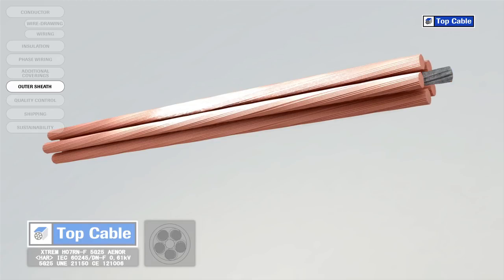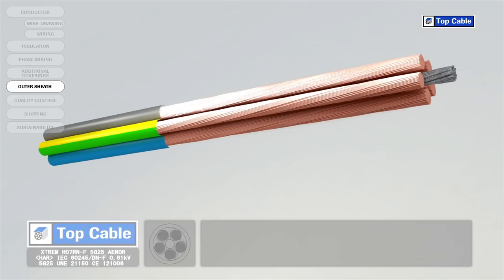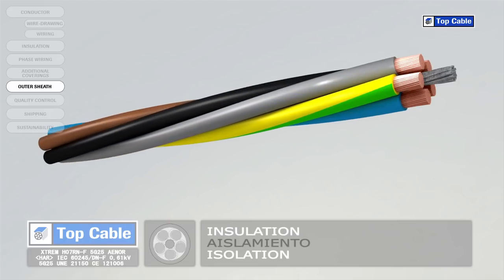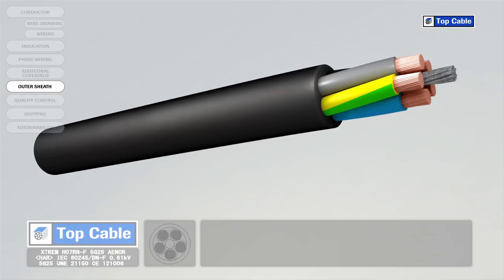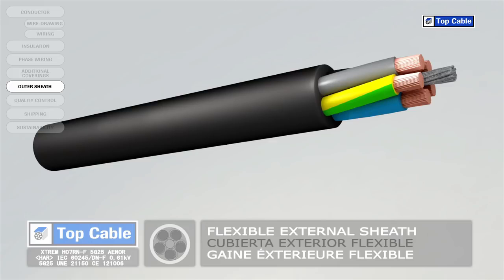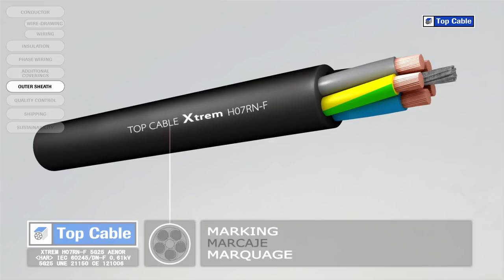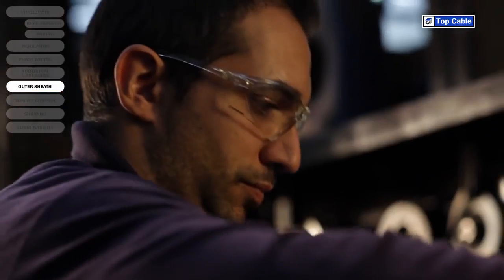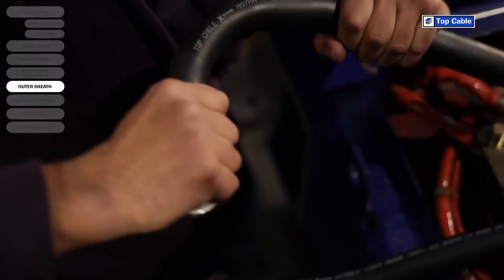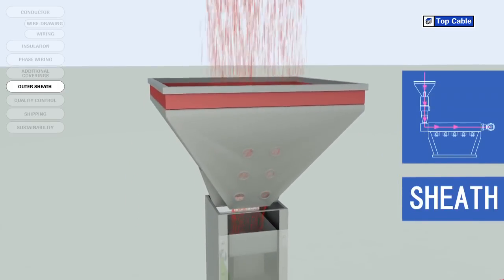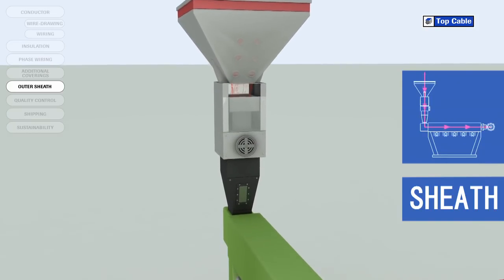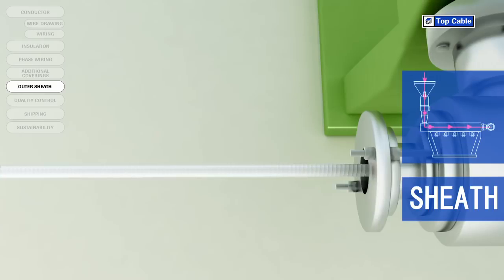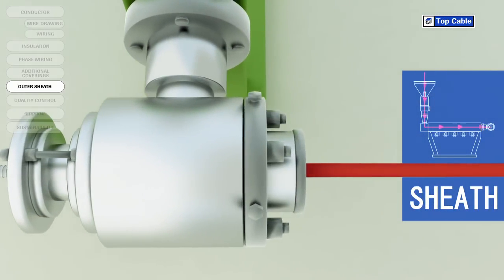Cables usually have an outer polymer covering for protection, called the outer sheath. The sheath protects the conductors and their insulation from external elements which may change their electrical properties, such as moisture. It also protects them from mechanical aggression which may occur during the installation of the cable. As with the insulation, the outer sheath can be made from a thermoplastic or a thermosetting plastic, and is applied via a process of extrusion at high temperature. The sheath may be made from different materials depending on the required protection level, the final flexibility of the cable, and the work environment.